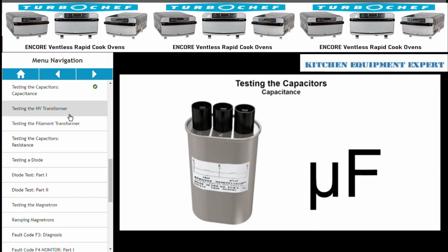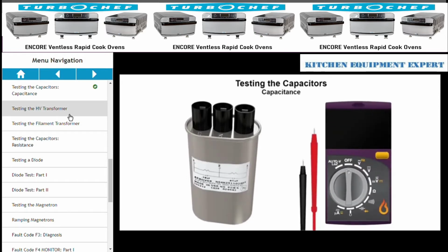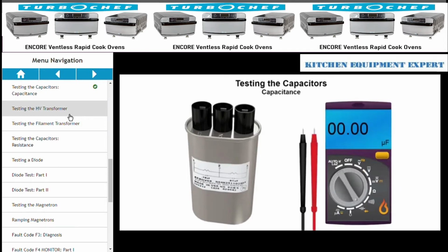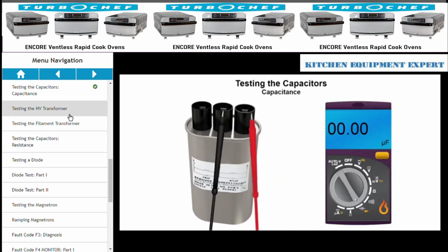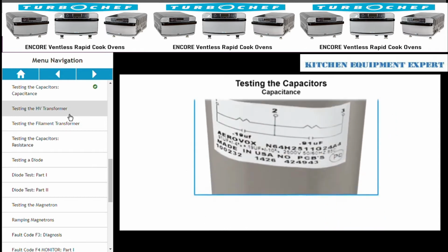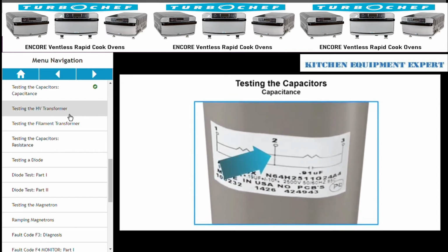Capacitors are rated in microfarads. If you have a digital multimeter with a capacitance setting or a separate capacitance meter, touch each probe to a terminal and check the reading. Give the meter a few seconds to charge the capacitor and stabilize. You should see a reading in microfarads that matches the label plus or minus 10%.